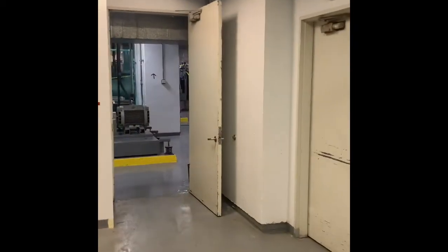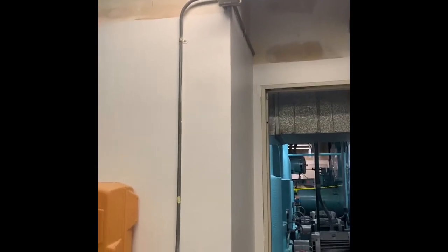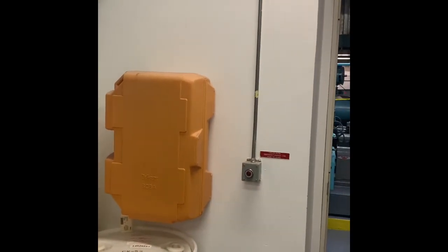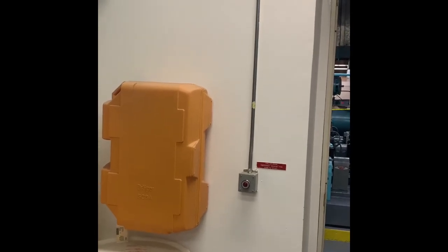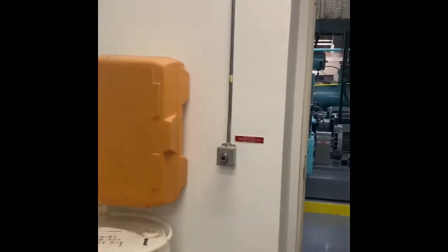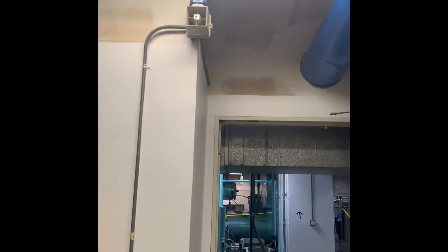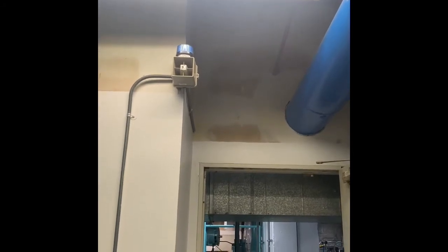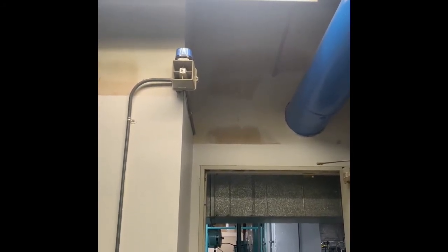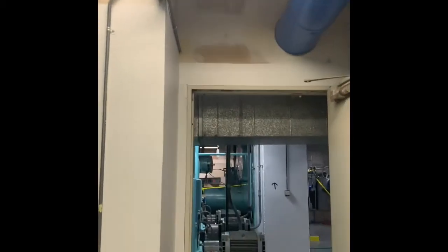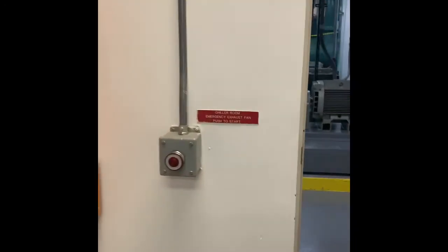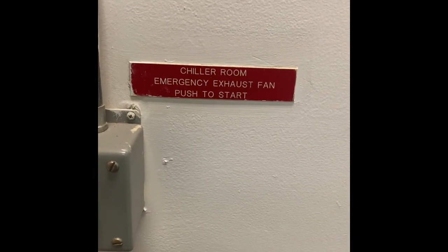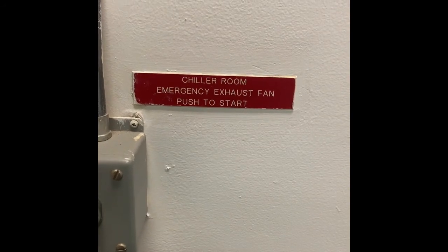All right, we're gonna head down the hall here, walk into our chill water plant. First thing you'll notice right outside the door, we got SCBA, self-contained breathing apparatus, in case of emergency or refrigerant leak. You'd want to put that on before having to enter this space. You also notice there's an indicating lamp, a flashing light, and an alarm. So for leak detection, that's connected to a leak detector in there. And then there's also a push button for emergency stop. It'll start the exhaust fan and it will automatically shut down the chiller.